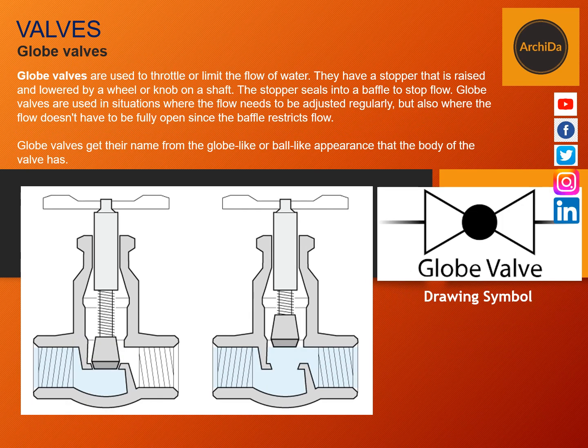Globe valves — similar to a gate valve, globe valves are used to throttle or limit the flow of water. They have a stopper that is raised and lowered by a wheel or knob on a shaft. The stopper seals into a baffle to stop the flow. Globe valves are used in situations where the flow needs to be adjusted regularly, but also where the flow doesn't have to be fully open since the baffle restricts the flow.